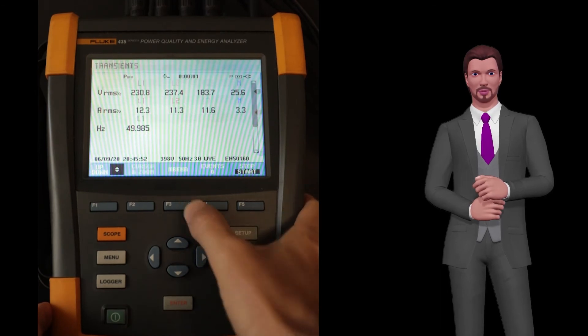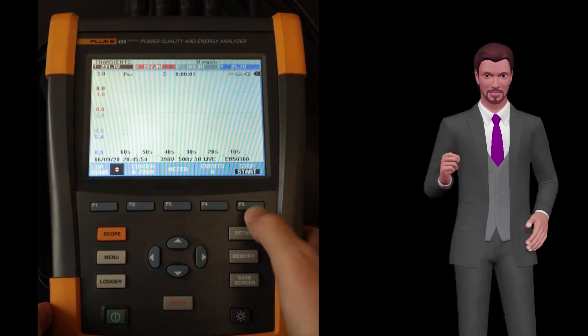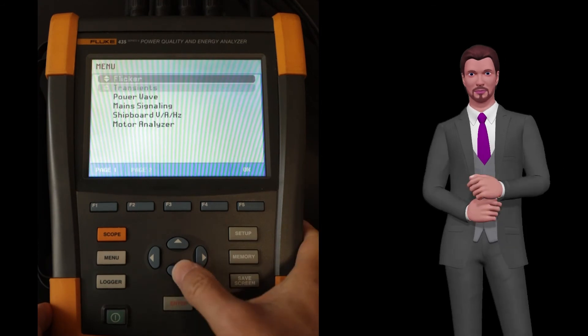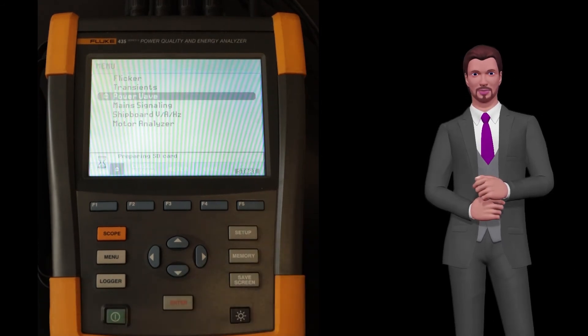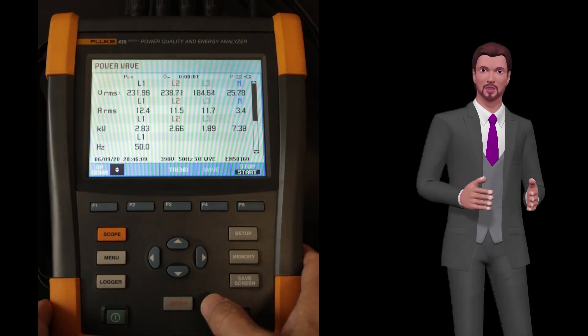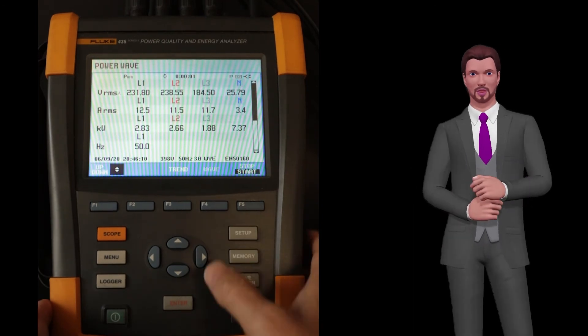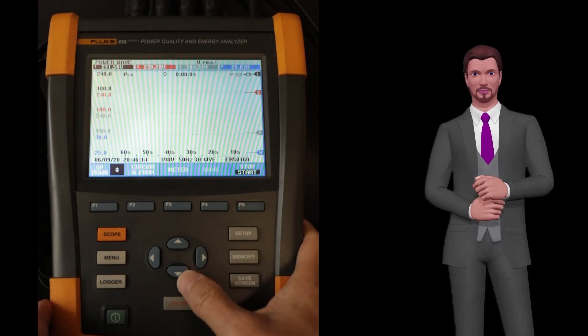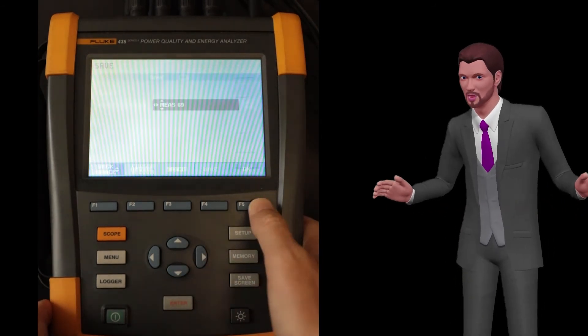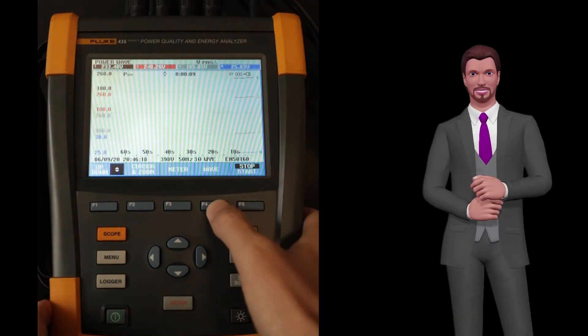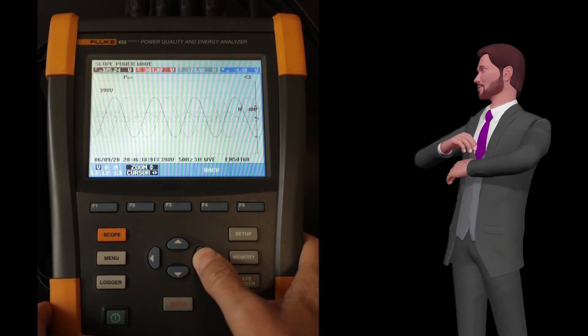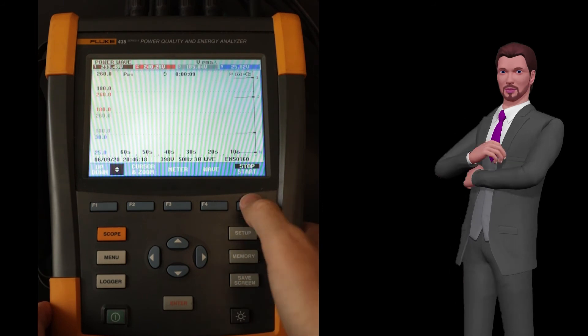The only thing we have to configure is the limit voltage value that triggers the capture of the transient. The next function, called power wave, allows us to record voltage and current waveforms without the need of any trigger, in blocks of up to 5 minutes each. It works like a memory oscilloscope. Waveform analysis can be key to determining the cause of certain problems, for example network transfers, disturbances at the output of inverters, etc.